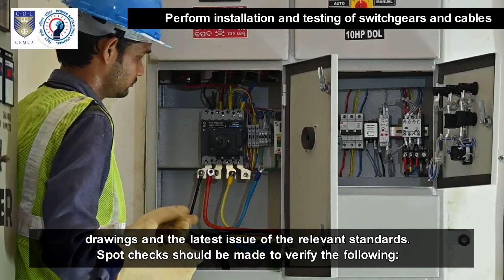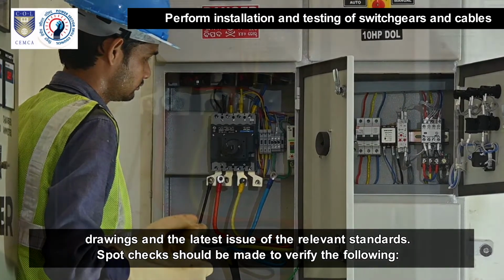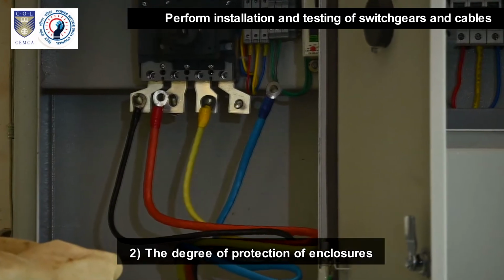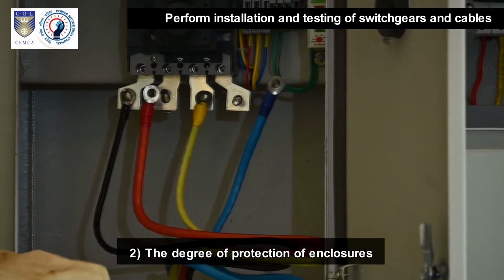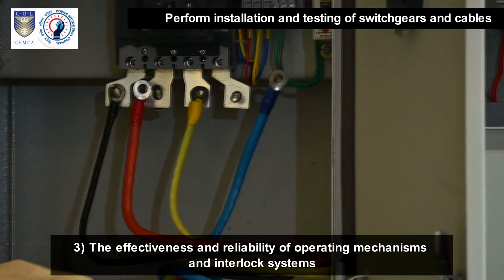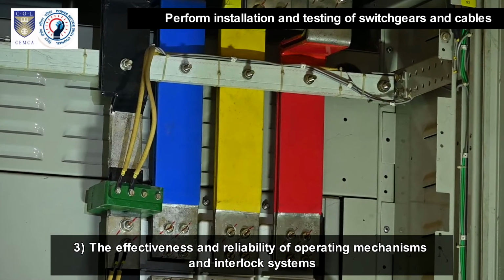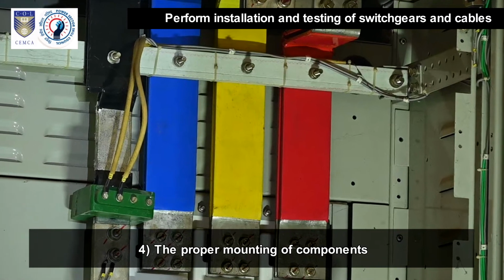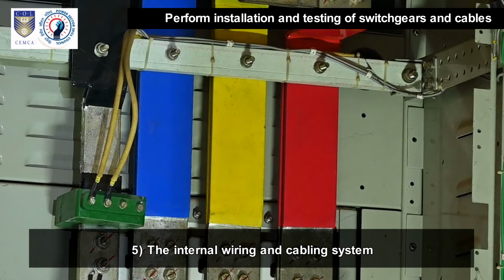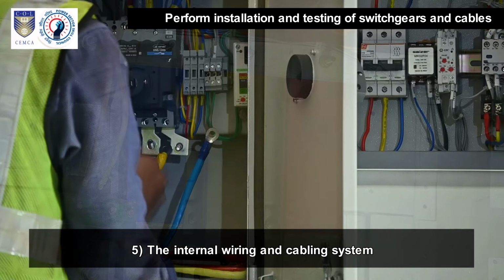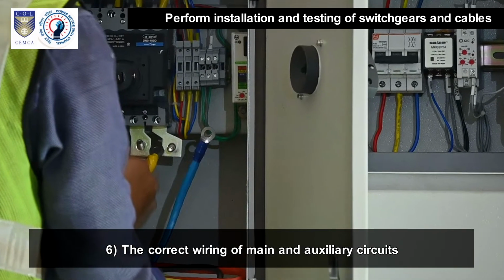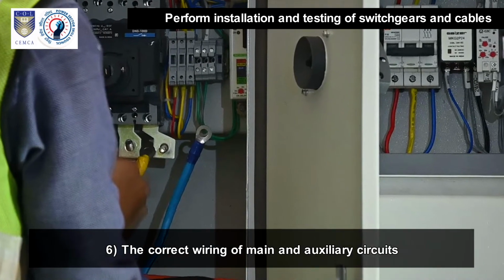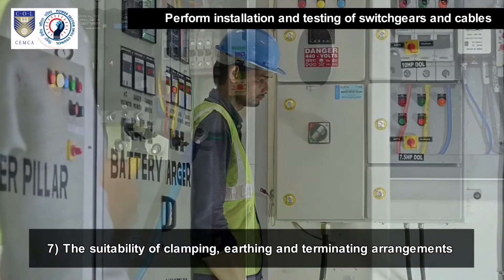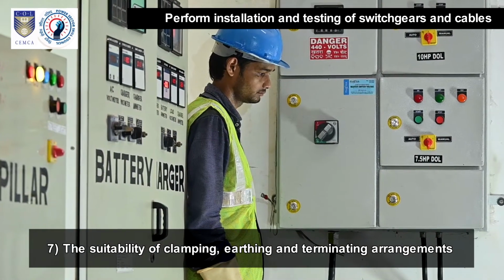Spot checks should be made to verify the following. 1. Dimensions of panel. 2. The degree of protection of enclosures. 3. The effectiveness and reliability of operating mechanisms and interlock systems. 4. The proper mounting of components. 5. The internal wiring and cabling system. 6. The correct wiring of main and auxiliary circuits. 7. The suitability of clamping, earthing and terminating arrangements.